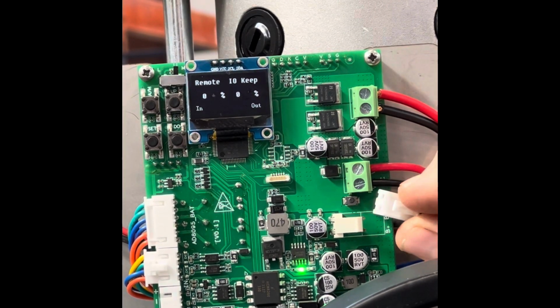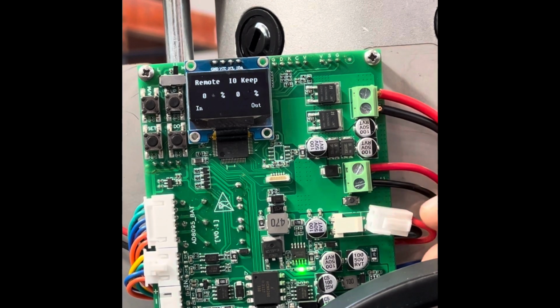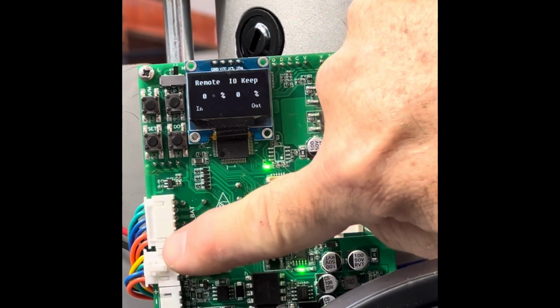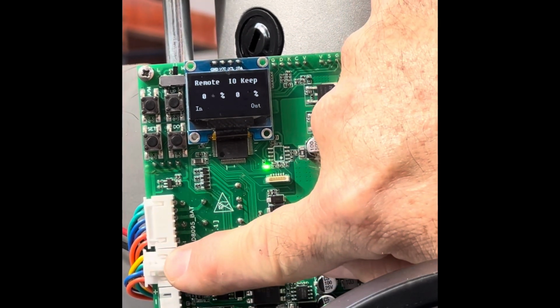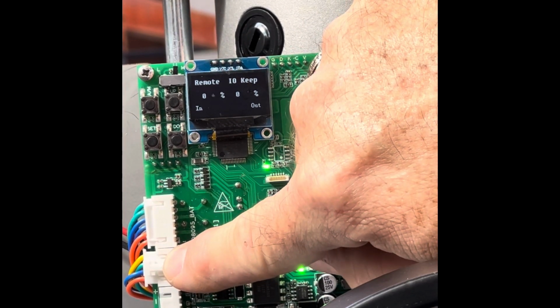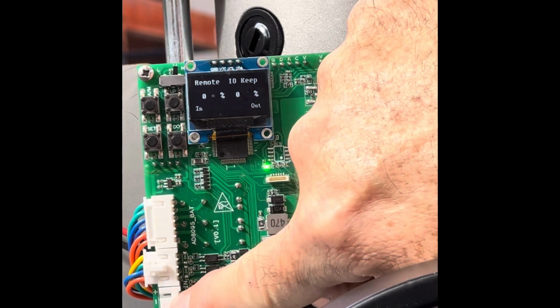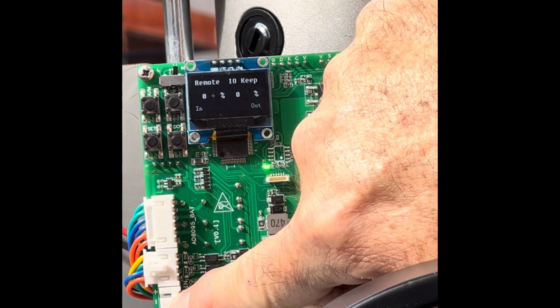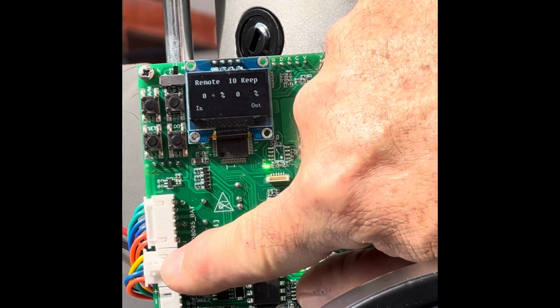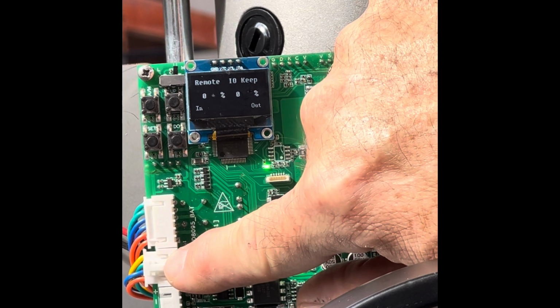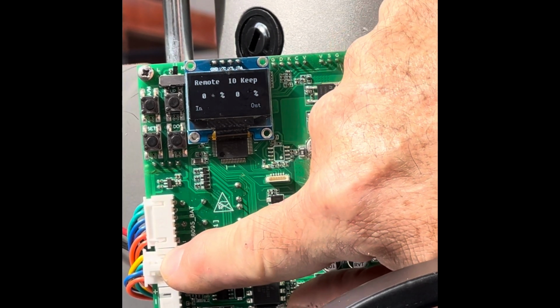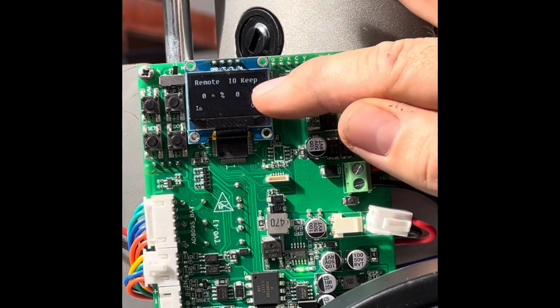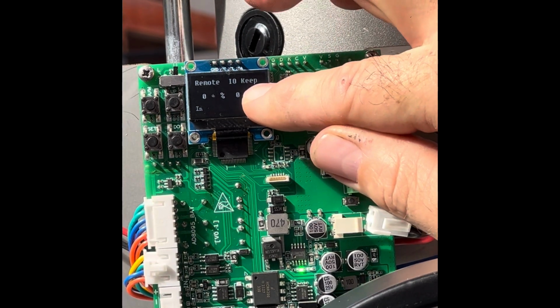Over here, this one's equipped with a battery backup. Over here, you've got 3 different plug ports. This plug port is for when you're doing a pulse or a keep signal. This port is for when you're doing a 4 to 20 milliamp signal. So right now, this actuator is set up to receive a pulse or a keep. And I know it's a keep signal because it says right up here, keep.